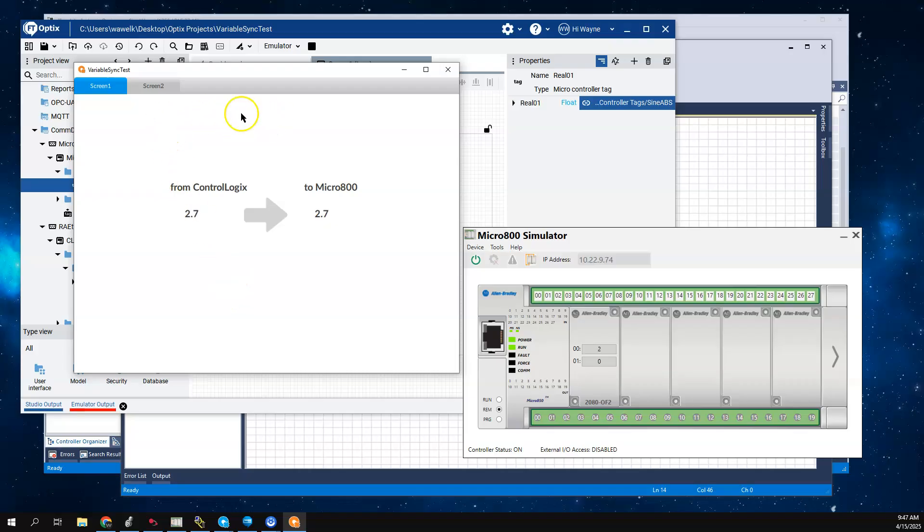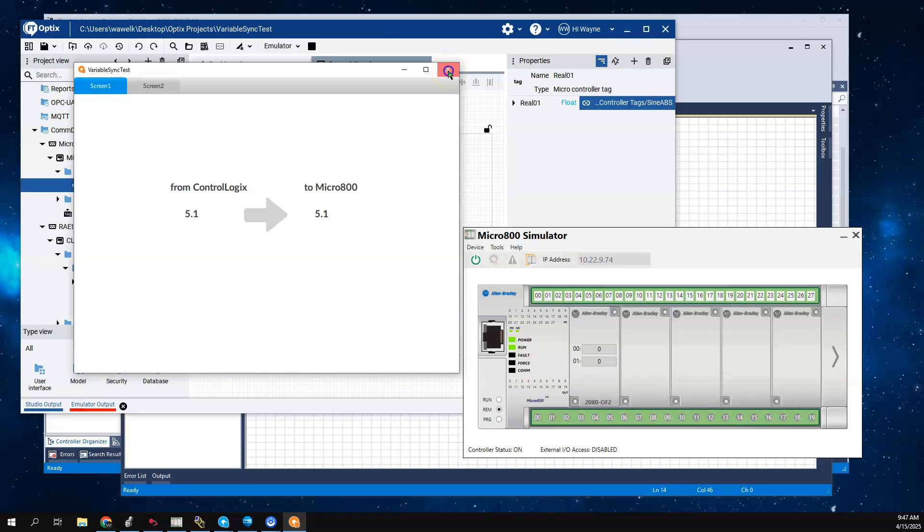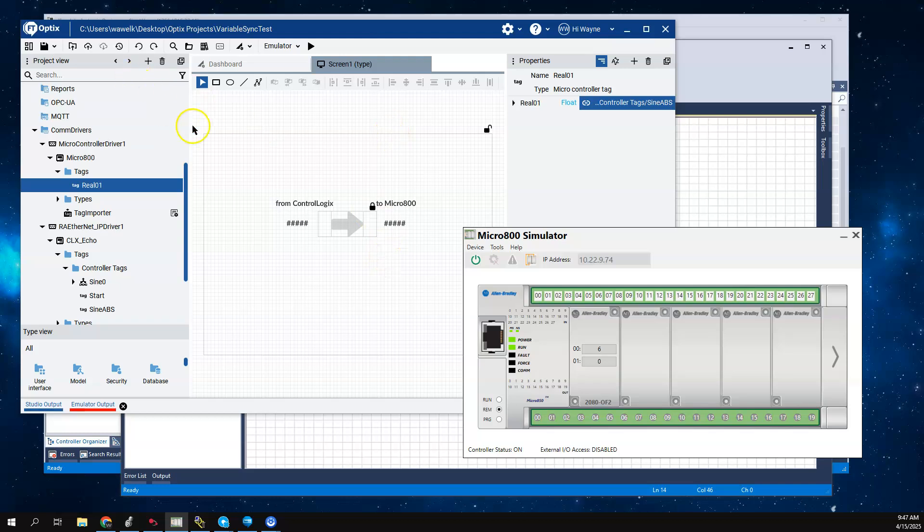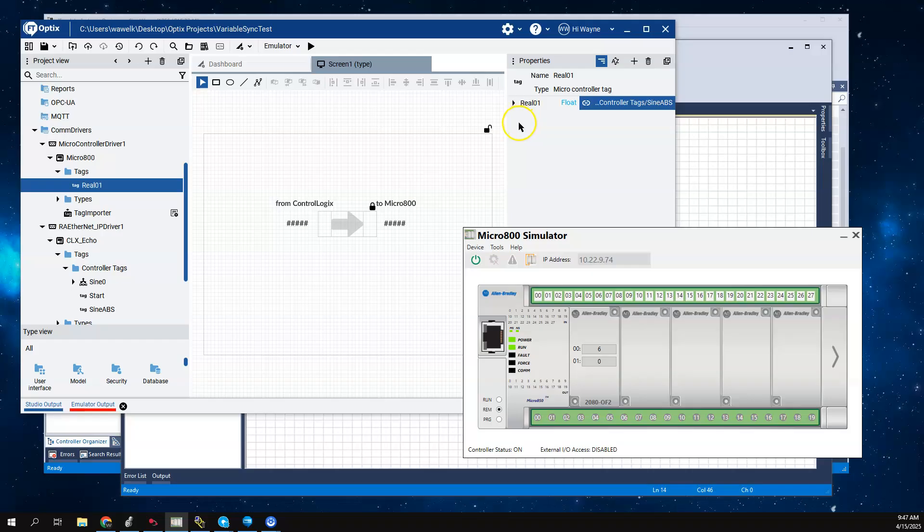If I move to a screen that doesn't have the sine tag on scan, it no longer moves the current value to the Micro 800. So only when the tags are on scan does that actually happen. Now one thing you could do if you're trying to do this situation again - if you're running headless, you would have no tags on scan essentially. One way to do this was to use that change event method.